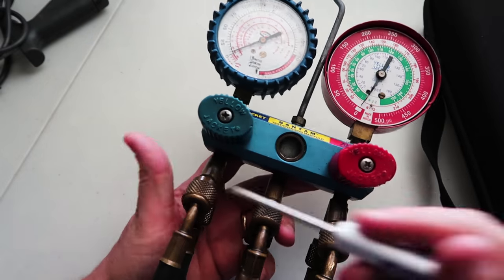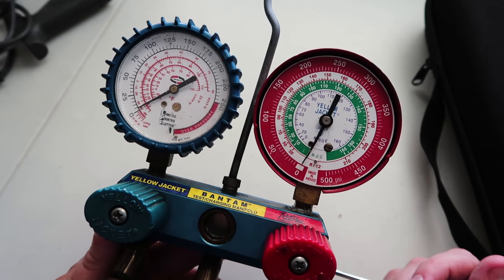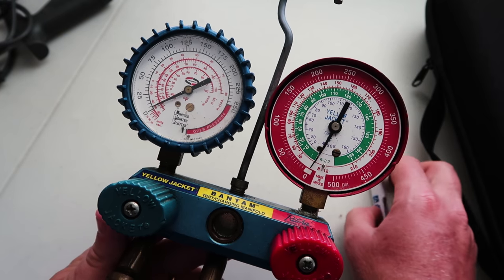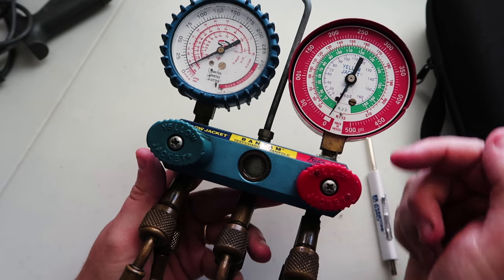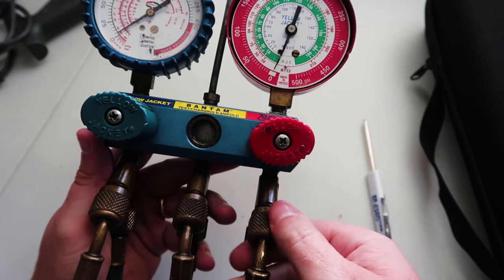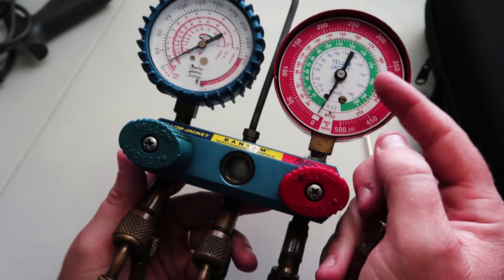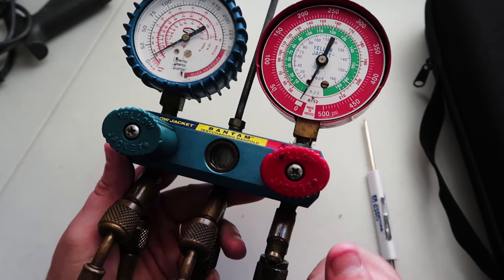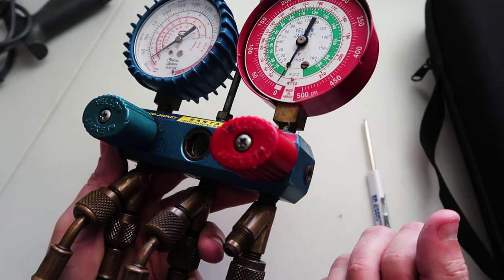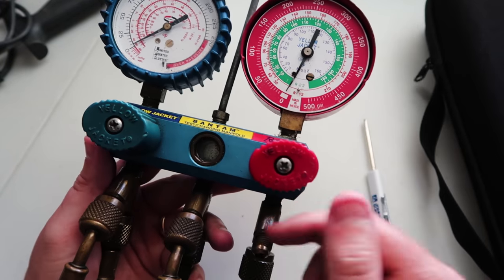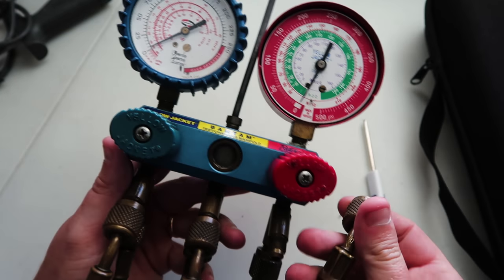For somebody who's brand new to looking at a refrigeration manifold, the first thing that they assume is that these handles somehow have something to do with what you read on the gauge, and the fact is that as soon as I connect this to a source of pressure, as soon as I thread this on, it's going to measure the pressure on the gauge. This handle doesn't have anything to do with pressure being read by the gauge. This is open through here regardless of how this handle is turned. What this handle does is it allows communication from the center to the other side, and we'll talk a little bit more about that in just a second.